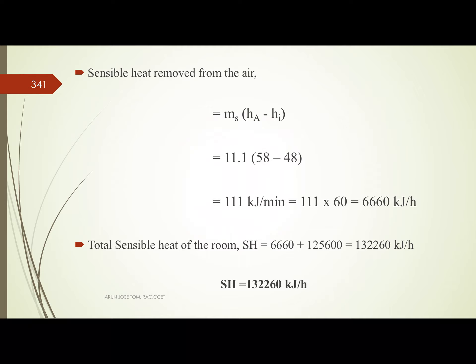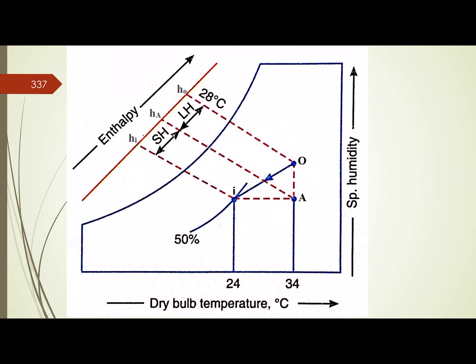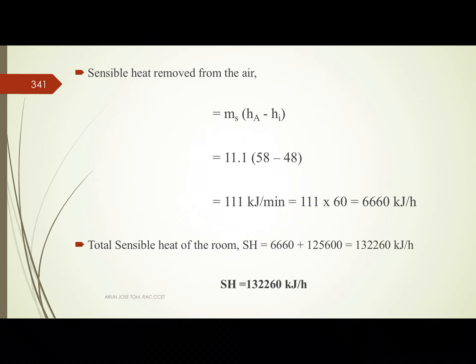The sensible heat removed from the air is calculated using the formula: sensible heat equals MS multiplied by (H_A minus H_I). The air enters at condition O and leaves at condition A. Latent heat is represented by H_O minus H_A.